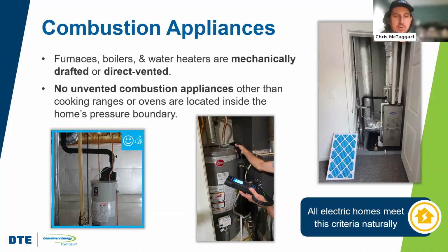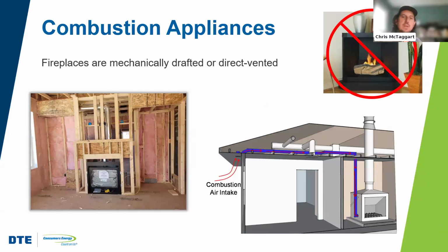You have a power vented water heater over on the left-hand side. Here in the center, we've got a standard atmospheric water heater. That doesn't work. That is neither mechanically drafted nor direct vented. And so for our climate, that is not going to work. You cannot have unvented or just atmospherically vented equipment. Obviously, all electric homes naturally meet this requirement because they don't have any combustion. So that's a pro for an all electric home.